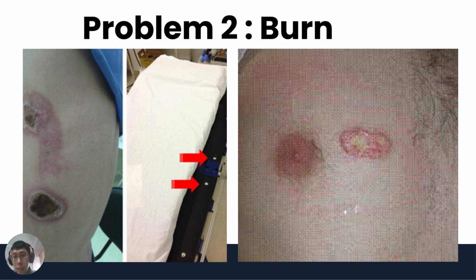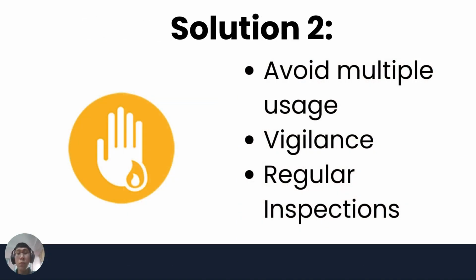Electrosurgical injuries also occur at sites other than the return electrode or active electrode. Burns to patients or operators can be caused by chipped, cracked, or damaged insulation on the electrode handles or cables, capacitively coupled leakage currents through electrode insulation, and alternate current paths to the ground. The solutions to burns: the first recommendation is to avoid multiple usage of the ESU on the same patient simultaneously to decrease the risk of patient burns.